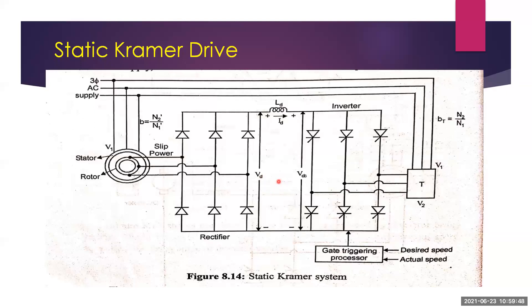In this method, the slip power is taken from the rotor and rectified by using a bridge rectifier to DC voltage by a three-phase diode bridge rectifier. The inductor Ld smooths the ripples in the rectified voltage Vd and also in the current Id. The ripples in the current can be minimized or suppressed by using this inductor, which acts as a filter.